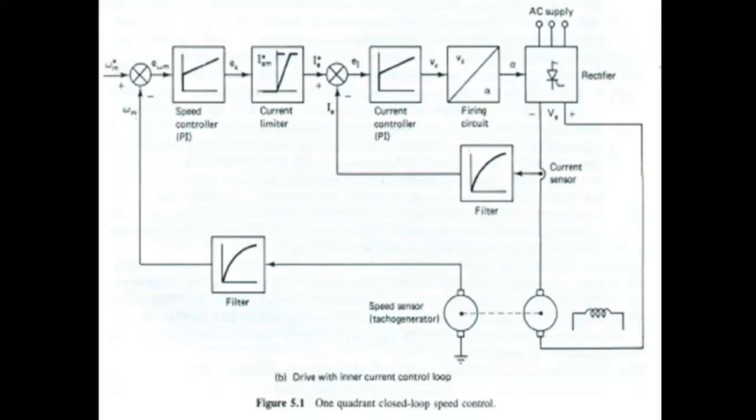So now both the schemes have different responses for the increase and decrease in the speed command. Suppose if you decrease the speed command, at the most, you can make the torque equal to 0. And it cannot be reversed because braking is not possible here. The drive will be decelerating mainly due to the load torque only.